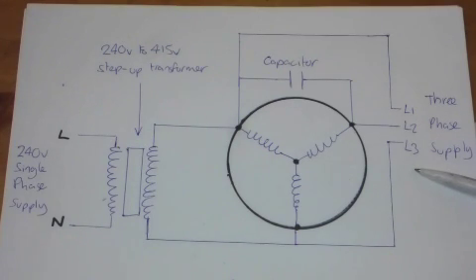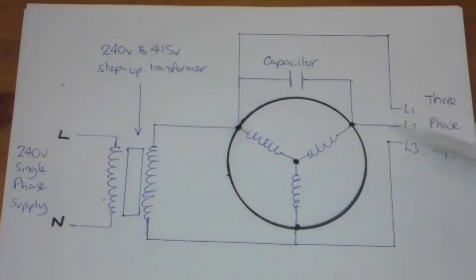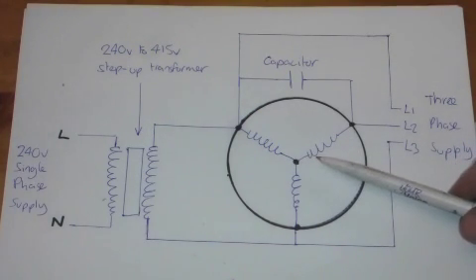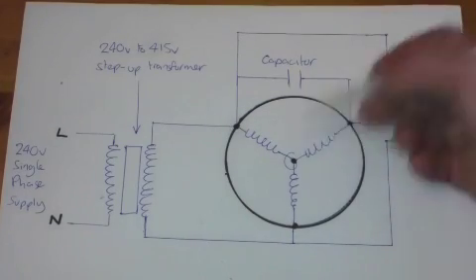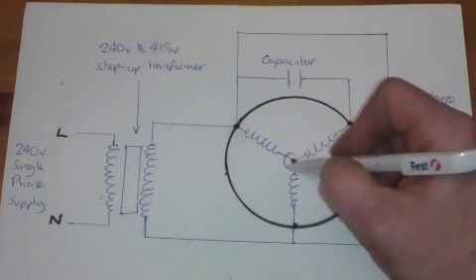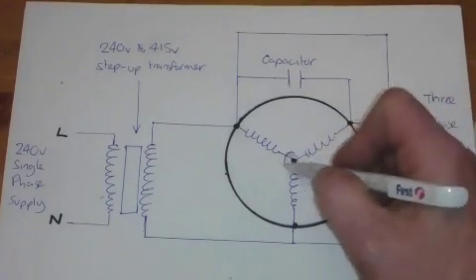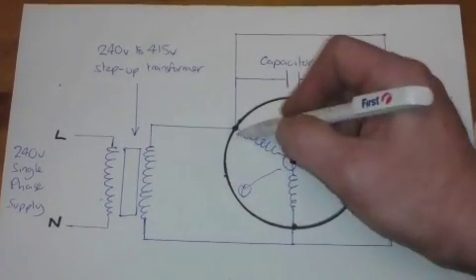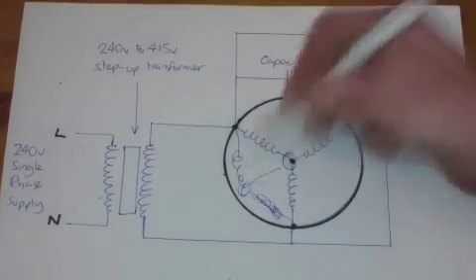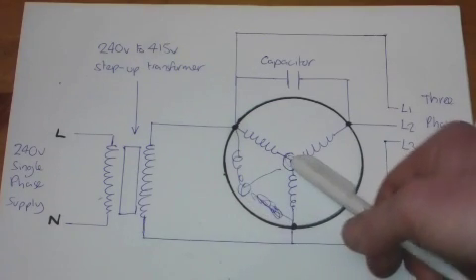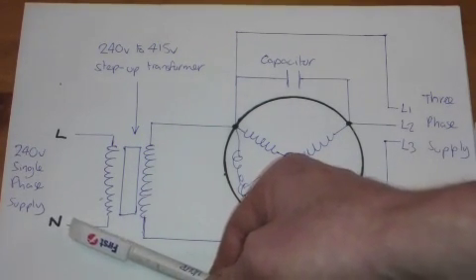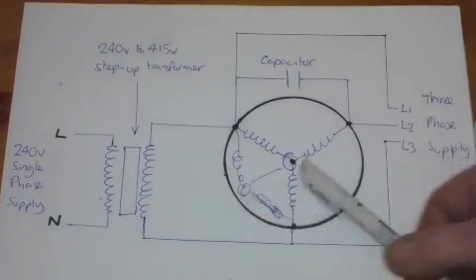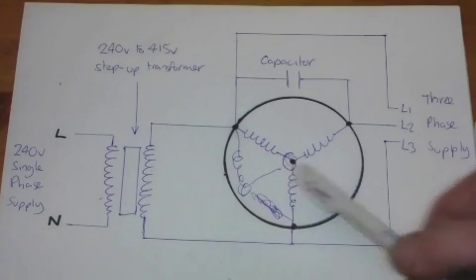If you don't need a neutral you might not think that's a problem and most people don't need a neutral I do. With the neutral gone and there it is isn't it the neutral here which should be our star point again isn't actually there the earth is there at zero volts but again the neutral we've got this floating neutral problem again haven't we. Neutral which should be zero volts same value as earth because of course you can touch neutral of your 240 supply and not get a shock I don't recommend it though neutrals not really where it should be.